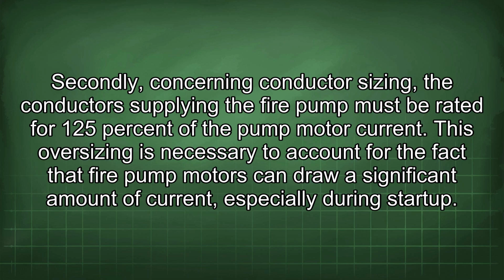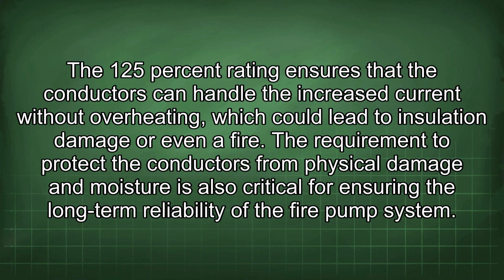Secondly, concerning conductor sizing, the conductors supplying the fire pump must be rated for 125% of the pump motor current. This oversizing is necessary to account for the fact that fire pump motors can draw a significant amount of current, especially during startup. The 125% rating ensures that the conductors can handle the increased current without overheating, which could lead to insulation damage or even a fire.